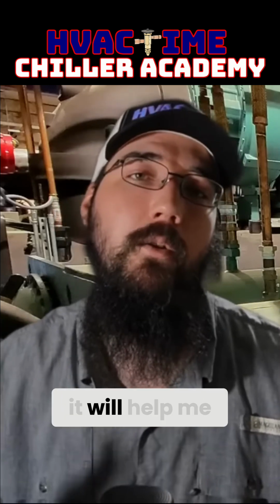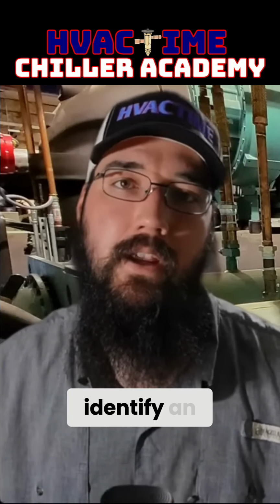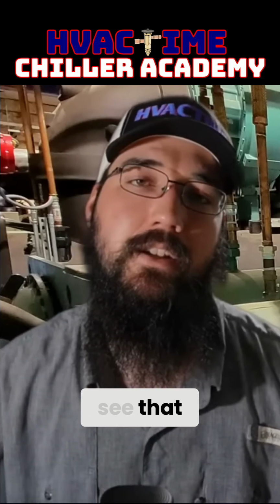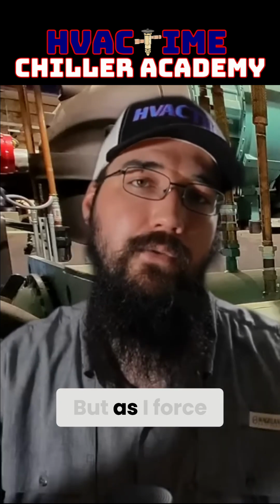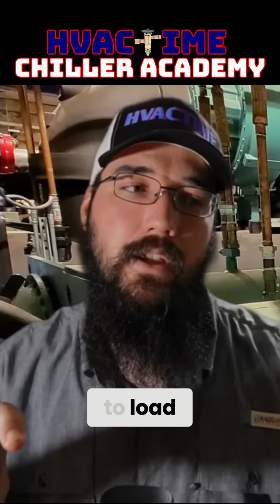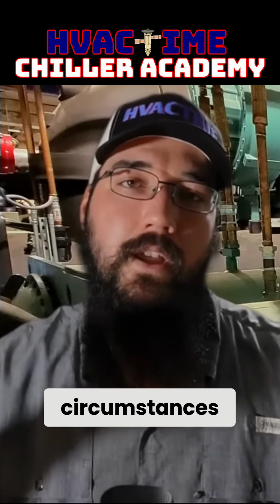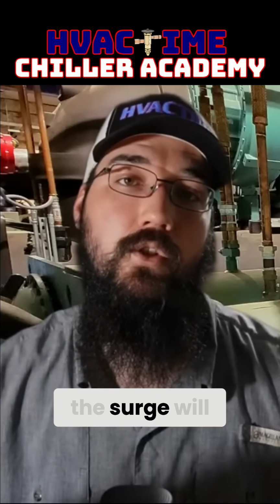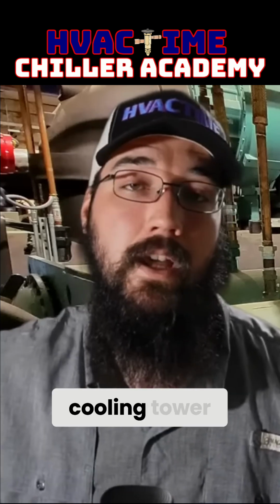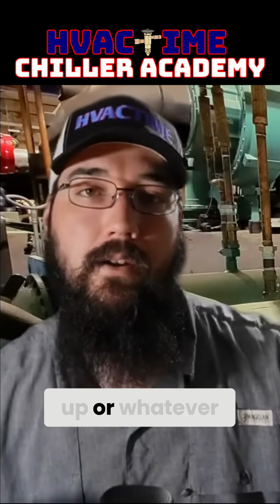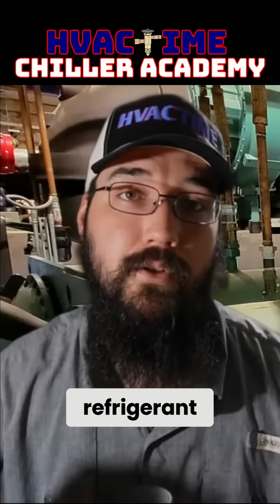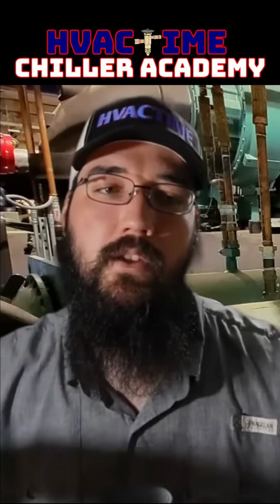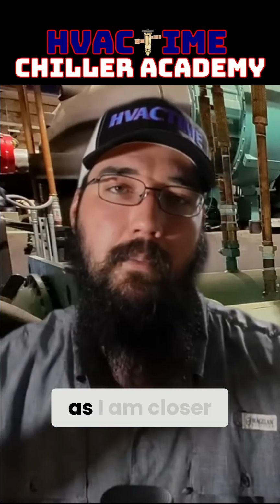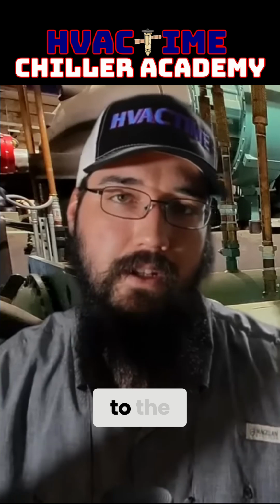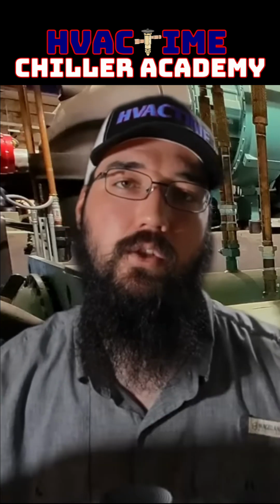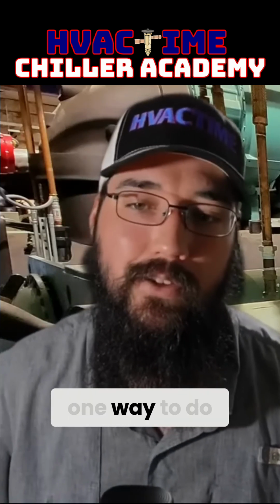Because if I can get to that surge line and see what my conditions are, it will help me more quickly identify an issue, because I may not be able to see that condition fully unloaded. But as I force that machine to load, the circumstances or conditions causing the surge will become more apparent, whether that be the cooling tower can't keep up, or maybe it's a refrigerant issue. Those things become more obvious as I am closer to the condition it's happening at. So current limit is one way to do that.